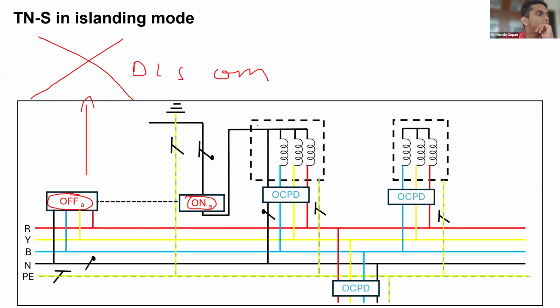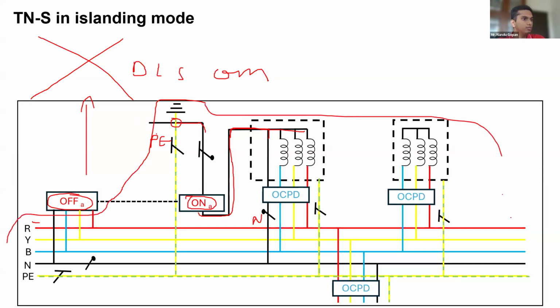So what is being done here is the neutral, and this is the system referencing conductor. This is the system referencing conductor of this source. So the source and the earth should be system reference, right? So what they do here is the system referencing conductor is being connected in this area, and from this area this will be a PE, and this will be an N. This will be a neutral conductor, and this will be a PE conductor. So this will be the system referencing conductor, and this will be on and this will be off. So this will be a perfect TNS supply, and from here everything is TNS supply. This will be in islanding mode.